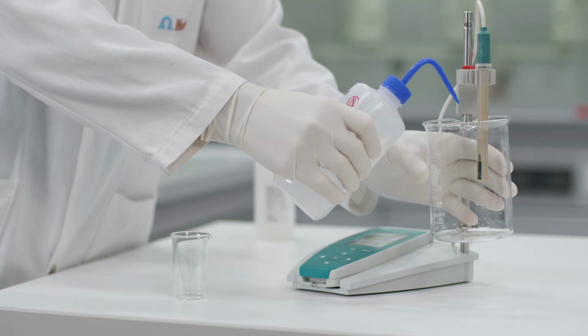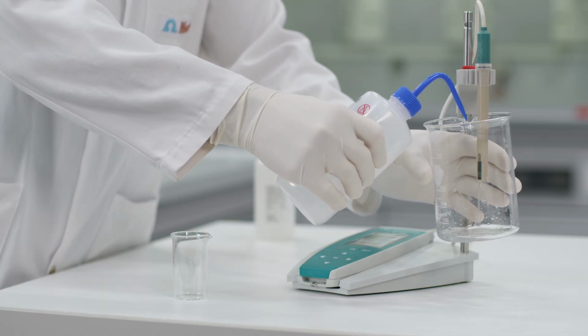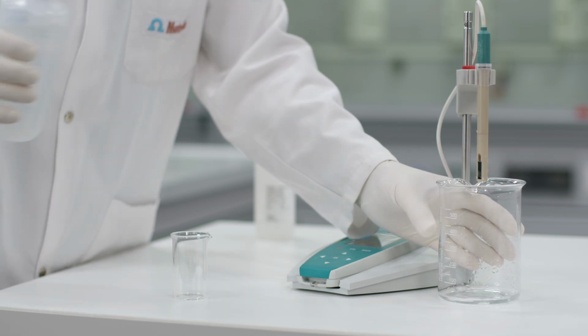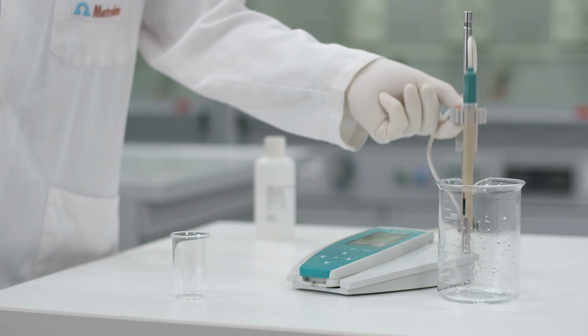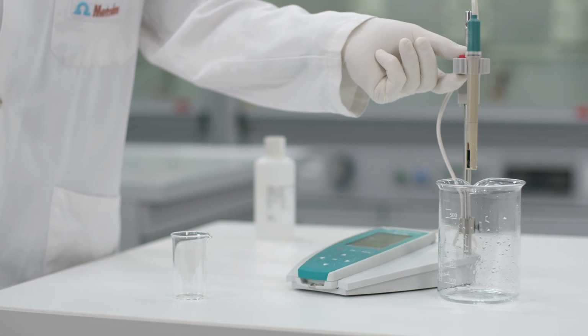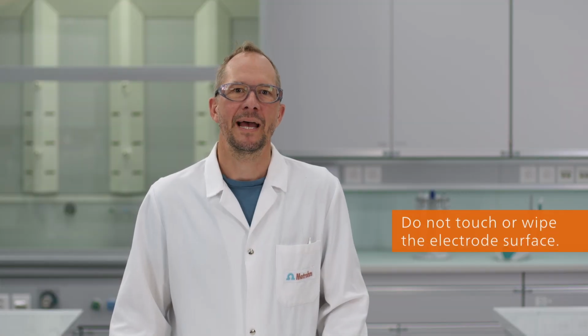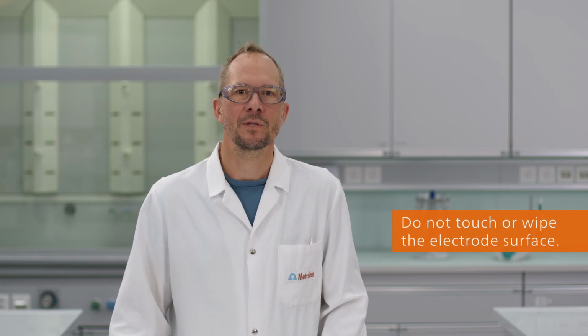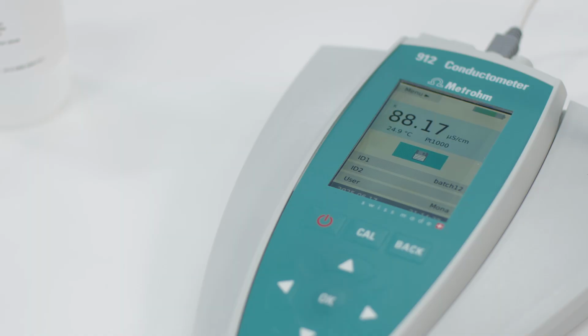Now, let me show you how to do the calibration. Rinse the conductivity measuring cell well with deionized water. Gently shake off excess water. Avoid touching or wiping the electrode surfaces inside the measuring cell, as this could leave residue. Select the measuring channel for conductivity on your meter. Start the calibration procedure by pressing the cal button on your meter.